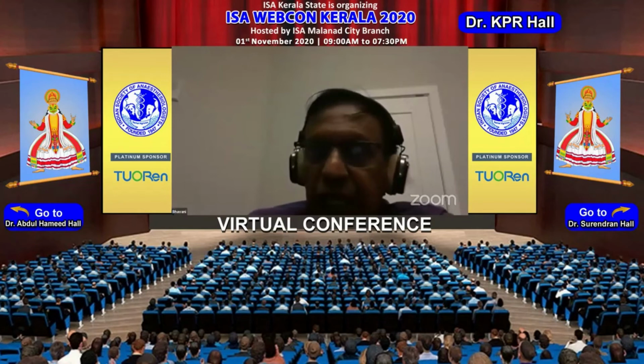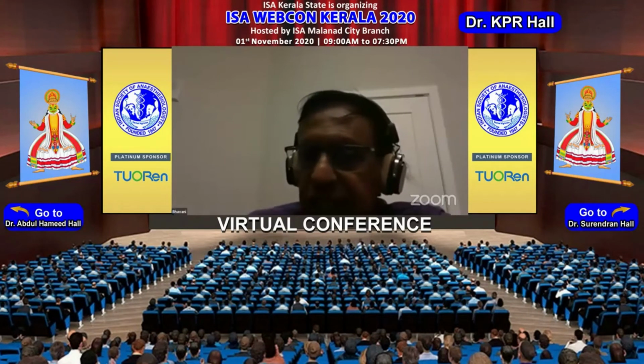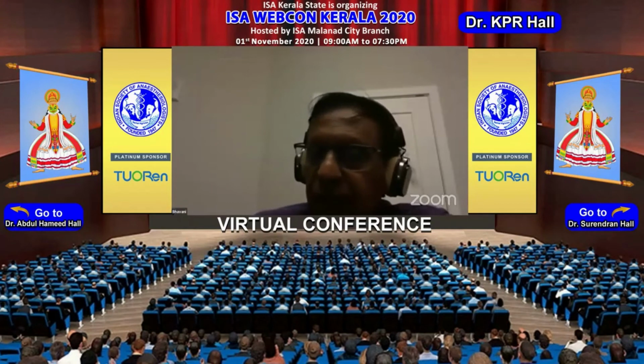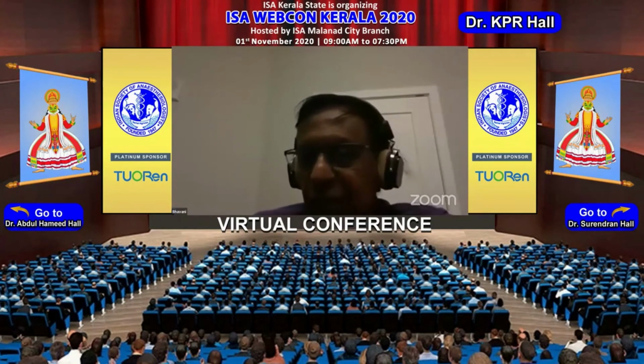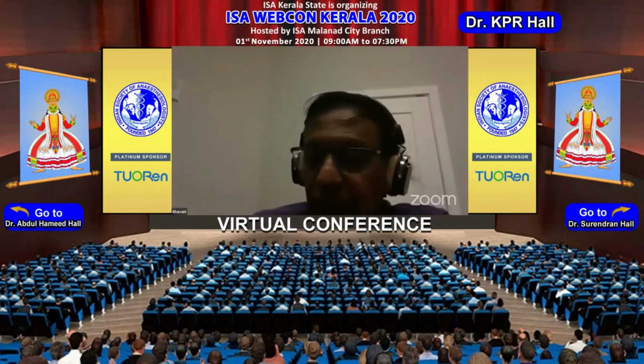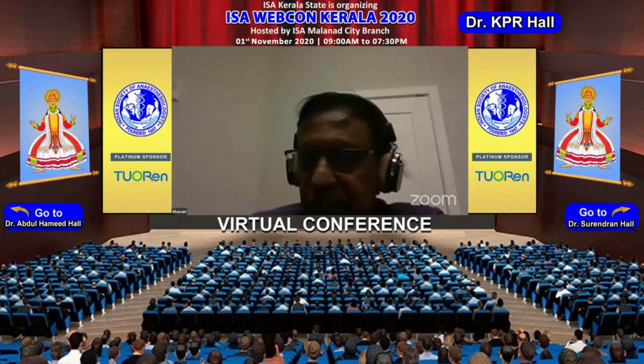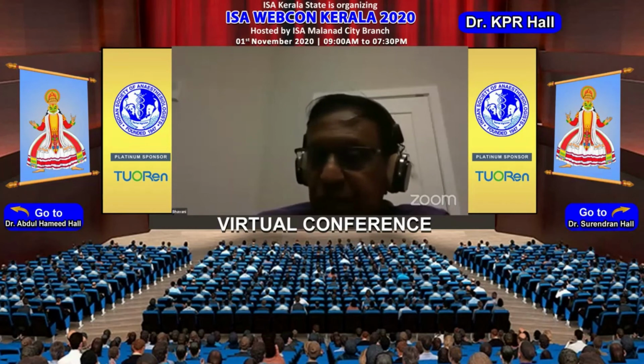Now, the recent technology which I showed you uses a side stream capnograph but gives you real-time images. The way it does it is they have incorporated the delay time into the software. So you actually get a volume capnogram using the side stream technology. Previously all volume capnographs used the mainstream sensor, because you need the flow instantaneously as well when you measure the CO2.